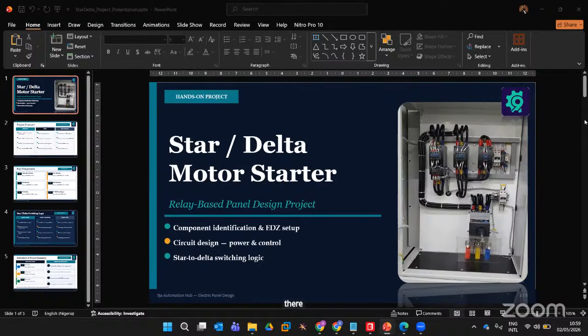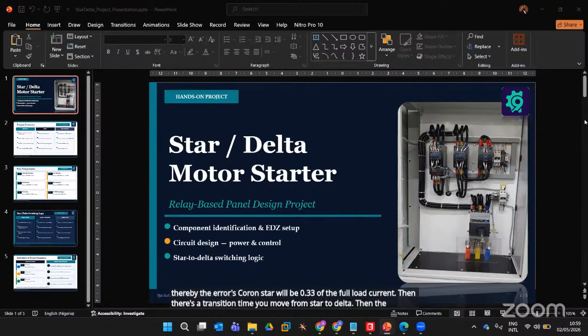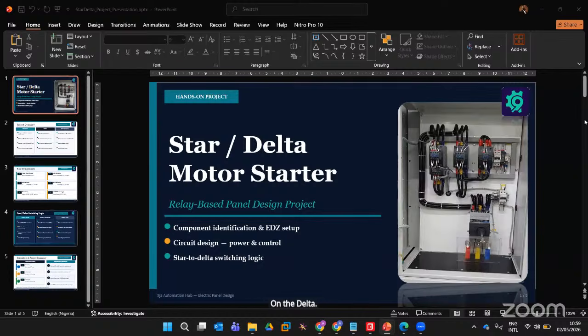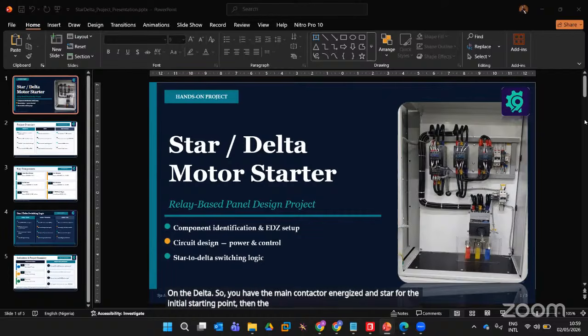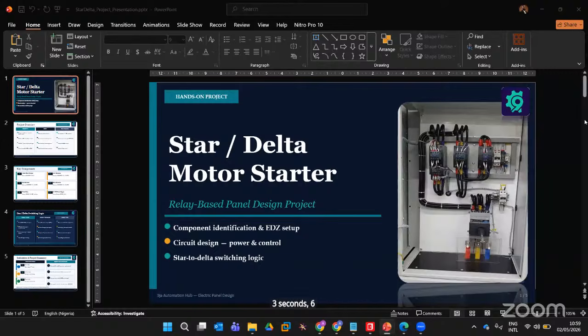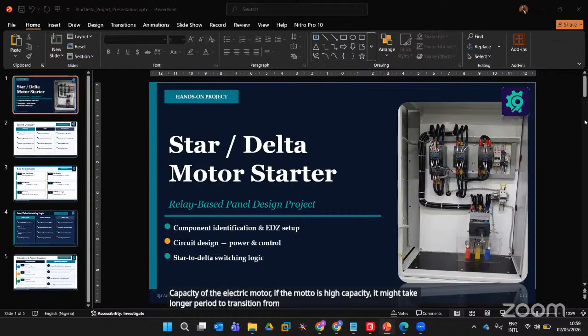Thereby, the inrush current on star will be 0.33 of the full load current. Then there's a transition time. You move from star to delta, then you achieve the current of 0.58 of the full load on the delta. So you have the mains contactor energized and star for the initial starting point. Then the transition from star to delta after a preset transition time, maybe 3 seconds, 6 seconds, depending on the capacity of the electric motor. If the motor is high capacity, it might take a longer period to transition from star to delta. That's just my basic knowledge of the star delta starter. Thank you. God bless you.